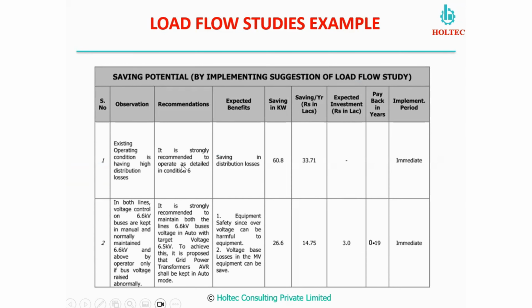Here, as I have shown you, by changing the mode of operation in which the plant was running, we have suggested just change the mode of operation, and there will be a saving of around 61 kilowatt without investing anything, without doing any corrective action in the power distribution system. Just what we have done, we have changed the mode of operation. So nothing has been done, and it has been implemented immediately. Okay, so I'm just giving an example. I'm not saying this can be possible in all of these studies, but in this particular case, we have achieved like this. But there are so many things in terms of saving which can be found through these studies.